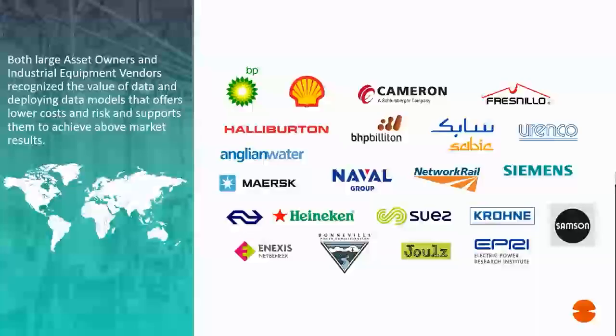Earlier on in the slides, I mentioned that a condition-based or predictive maintenance program makes sense if the accuracy of predictions is 80% or above. This means that 2 out of 10 predictions are actually off, or actually false. And this will improve over time as the quality of your data improves. But if you have too many false positives early on in the project, it is very often not motivating for the people involved to continue with it. So the first step the company needs to take is to make sure that the data quality is at a high level. And the quality of data stored in data historians is very often of a high level, because reporting systems and other business processes rely on the quality of that data.